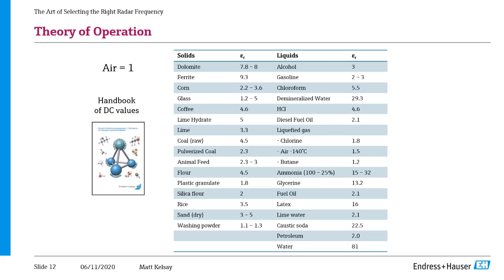So generally, liquids have higher dielectrics than solids. Anything above 10 or so is considered very high dielectric and is a very good candidate to use a radar device for. In the range of, say, 4 to 10 is kind of that mid-range, still a good candidate for radar, definitely doable. Maybe a couple things you want to take a look at just to make sure it's a good application. And the measurement starts to become a little more difficult, not impossible, but more difficult around a dielectric of 2. So at that point, you kind of need to look at the application as a whole and make sure the installation is going to be correct and that process conditions will allow for a good, reliable measurement.